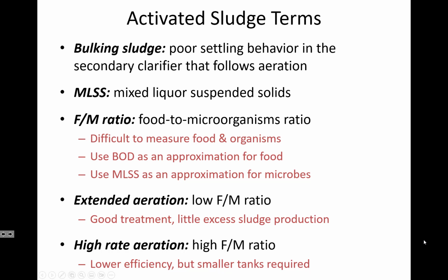And so, although you may not think that it's going to have an influence directly on the BOD removal in the aeration basin, there is an indirect effect that if you can't settle the sludge well, then you're not able to collect it to recirculate. So bulking sludge is a problem that actually can affect the BOD removal, and it's not just an issue of convenience or variability of the clarifier performance.